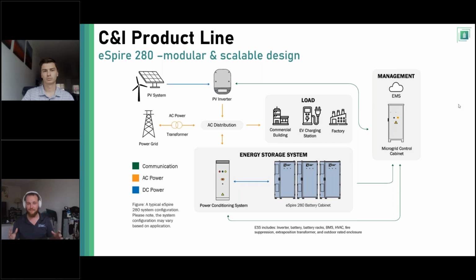So we're able to operate the PV when there is an outage, helping to energize that system. You can see the green lines there from the PV inverter and from the PCS to the microgrid control cabinet. We're sending all the data from CTs, all the production data, feeding it to our control cabinet and up into the cloud so you can view it on that online dashboard. So in a nutshell, this is how this system will AC couple to feed the loads on the right-hand side of that distribution panel.